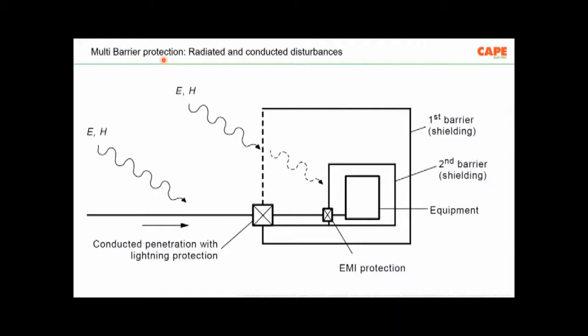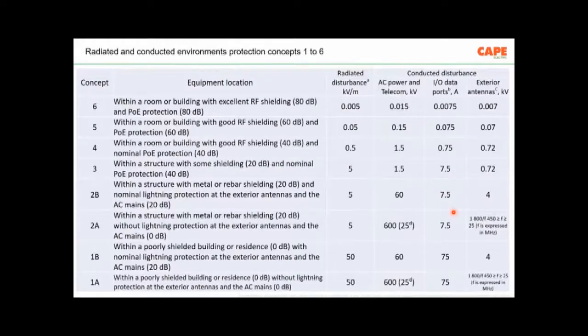Earthing, for example, means equipotential bonding. If you make a very good equipotential bonding system, then your equipment will be very well protected. Now, with respect to the conducted and radiated surges, this is a symbolic representation. Each one is talking about the first barrier, second barrier, and the equipment. So there are barriers at various levels. Now, IEC is recommending a six-point concept protection plan for a facility.